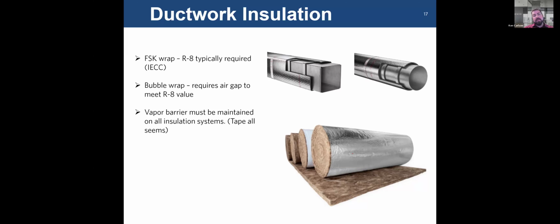But regardless, in order to obtain that R8 value, you need to actually have spacers. You need to put an air gap between the bubble wrap and the ductwork. You do this by taking another small section of bubble wrap, taping it to the ductwork, and then wrapping around that. It creates an air gap in between here. Something to note: depending on where you're at, it could be enforced by local code as well.